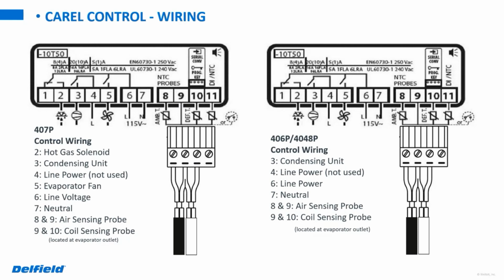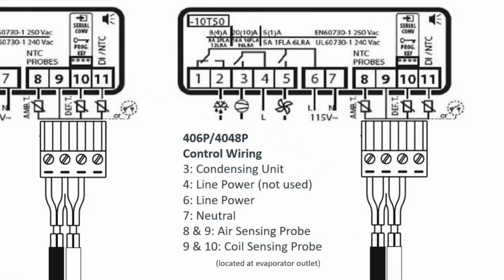With the cooler, it's a little bit different. Big difference being there is the evaporator fans are going to run 24/7. As soon as you plug that unit in, the fans are going to be on. They're going to run throughout defrost. They're going to run while the unit's cooling during an off cycle. There should be no time where the evaporator fan is not running on the 406 and 4048. There is no heating element or hot gas solenoid for defrost on those. Probes are exactly the same as the freezer.